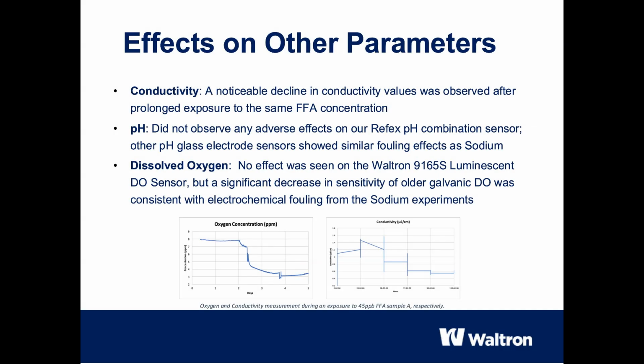We also wondered whether these effects could be transferred to other measurement parameters. The results confirm that this is a systematic problem of electrode contamination. We observed a similar effect in conductivity measurements. Over the test period, we observed a noticeable decrease in the measured conductivity. This is because the insulating FFA film also coats the conductivity electrodes and impedes the flow of ions, which the device incorrectly interprets as lower conductivity.